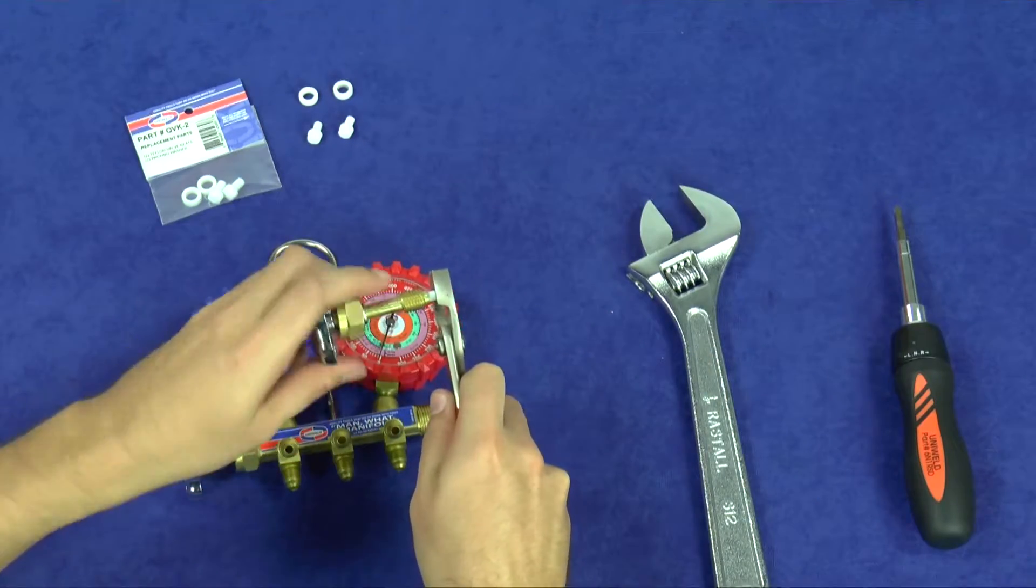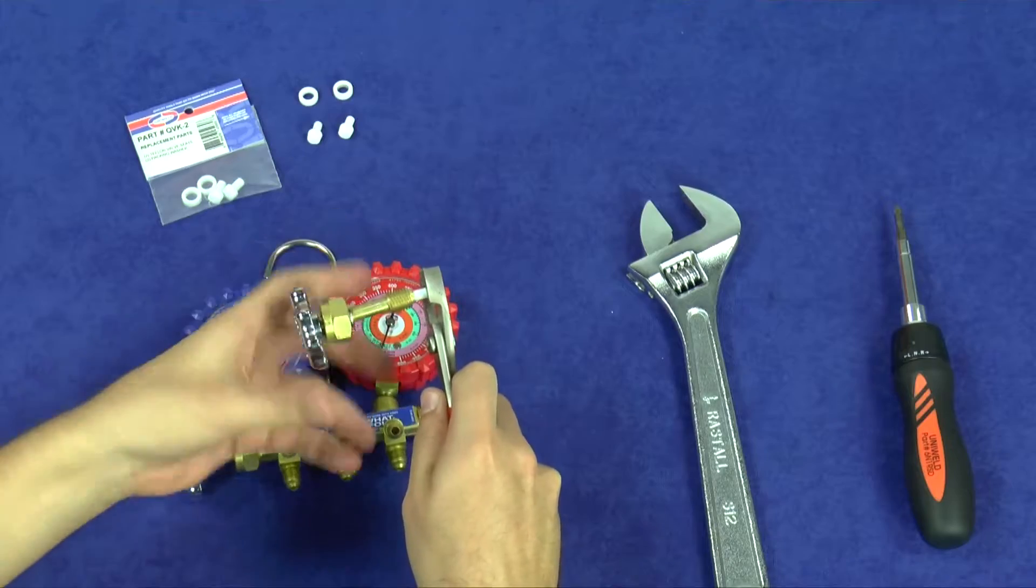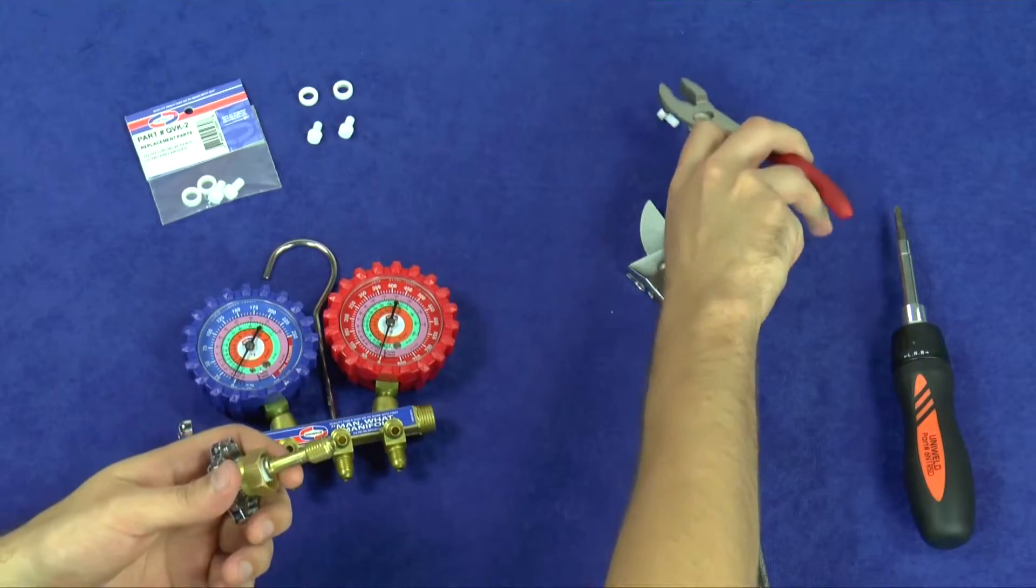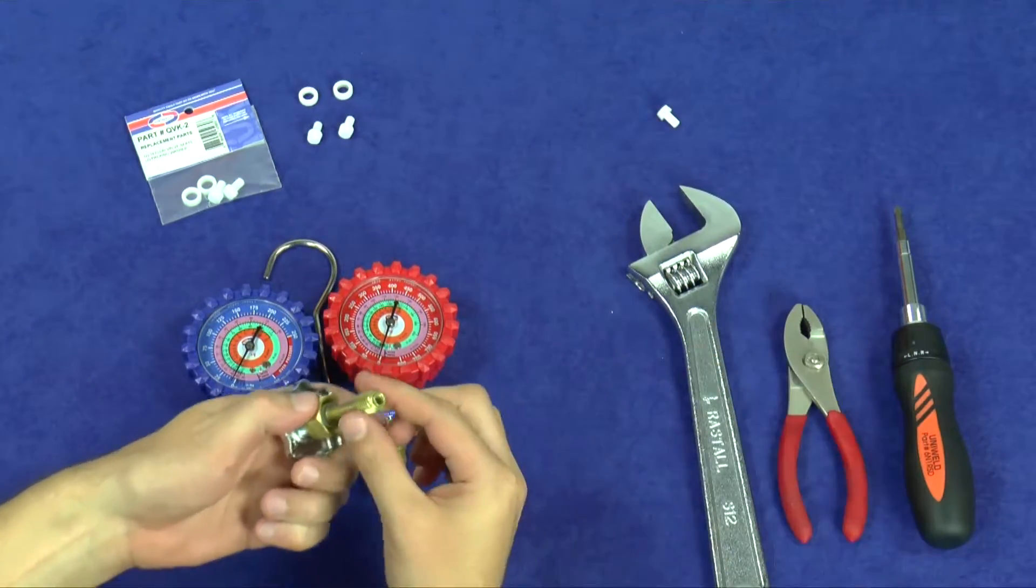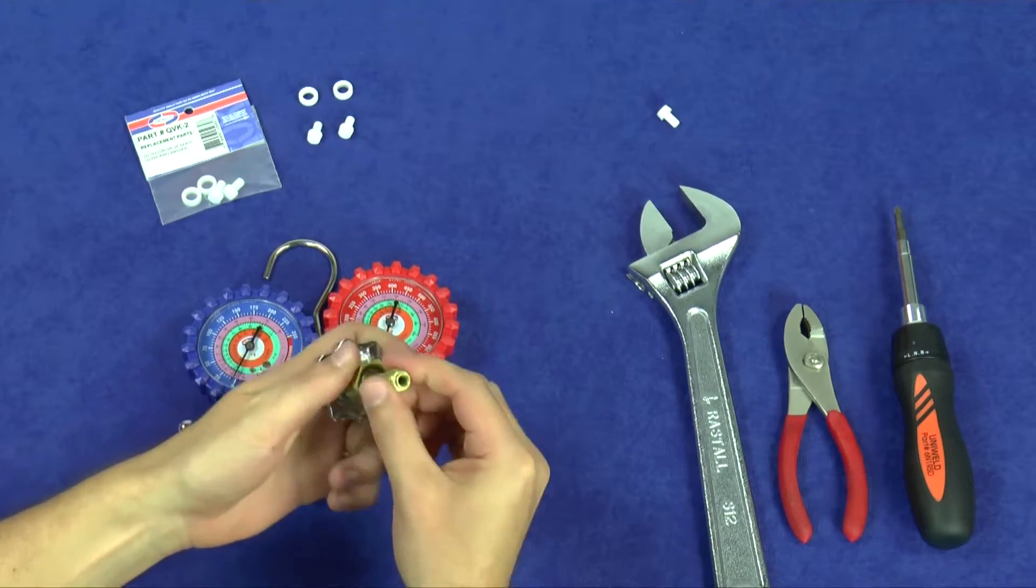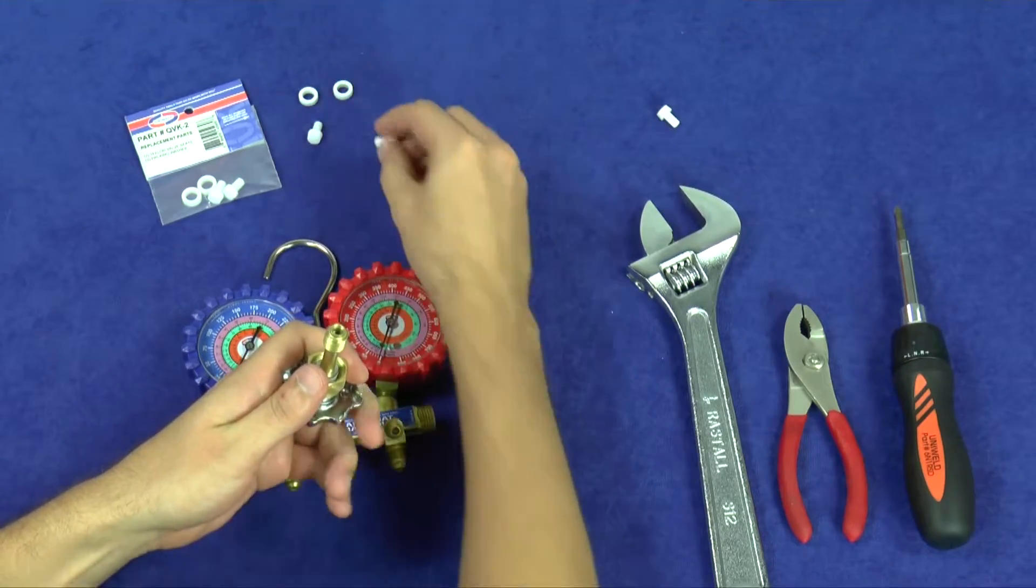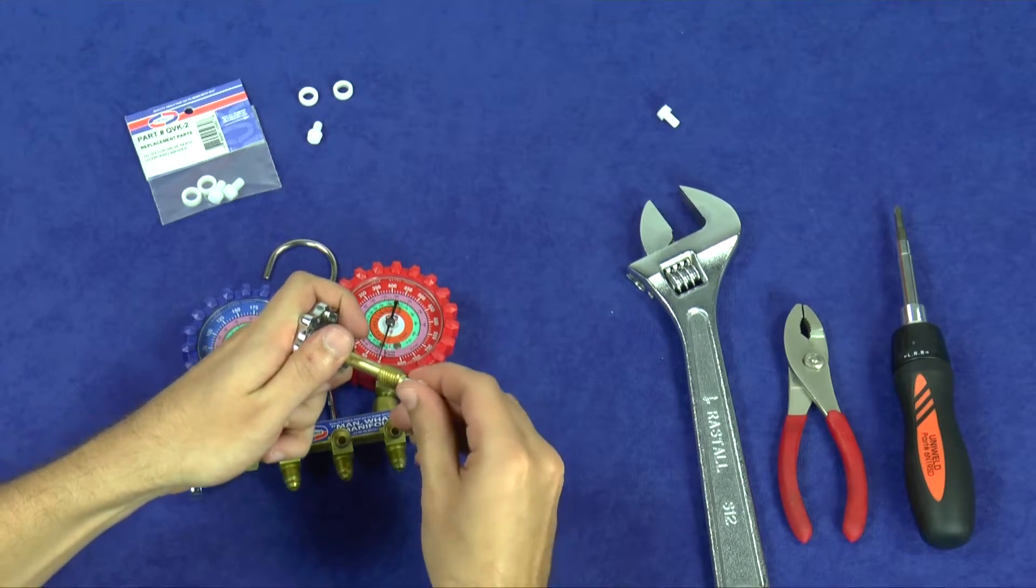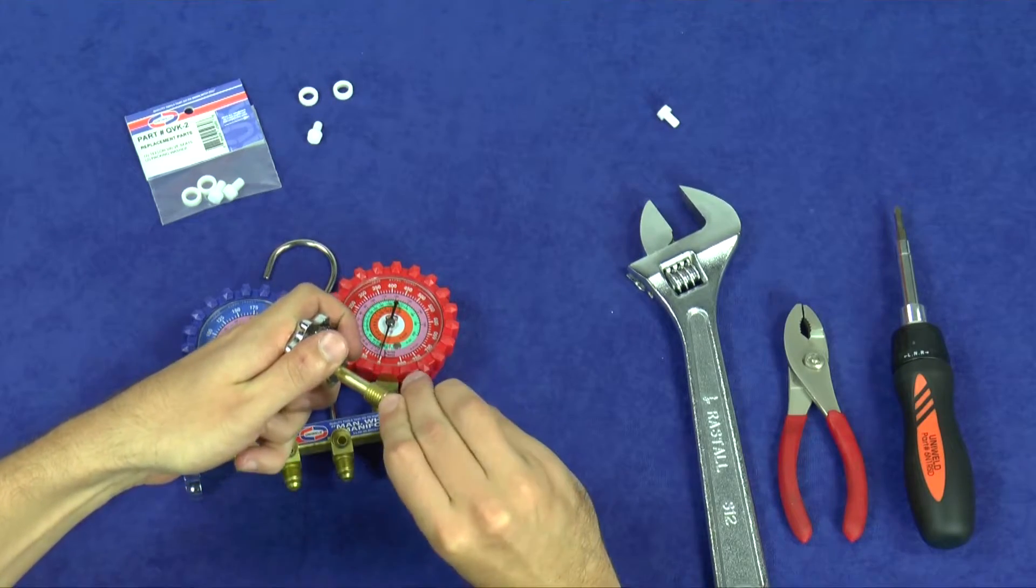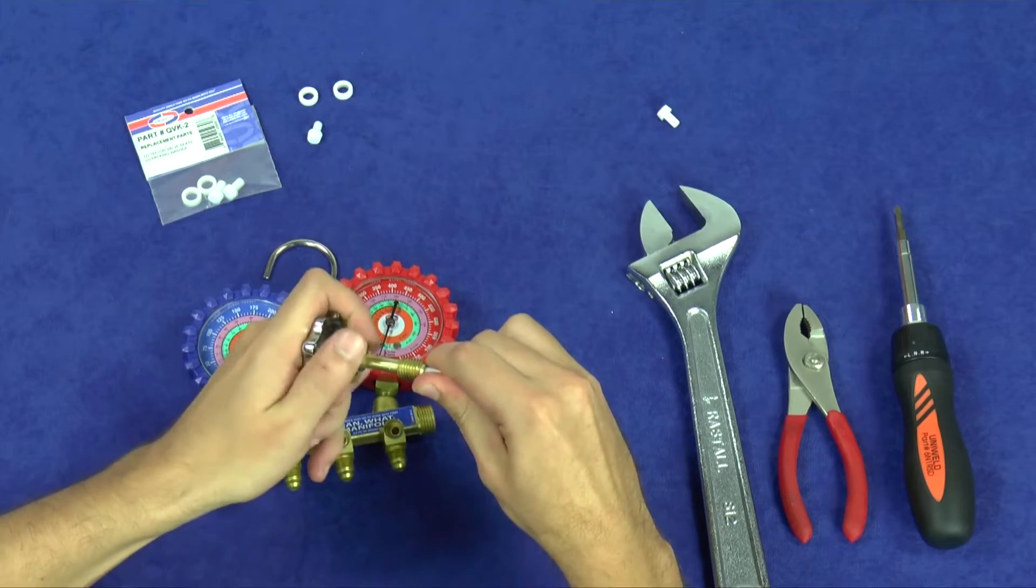Using pliers, unscrew the Teflon seat from the valve stem. The threads inside the valve stem are reversed, so removing the Teflon is clockwise and screwing it in is counterclockwise. The new Teflon seat does not have threads—it is self-tapping—so be sure to thread it straight into the end of the brass stem.